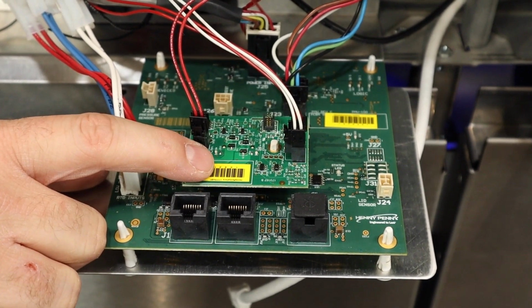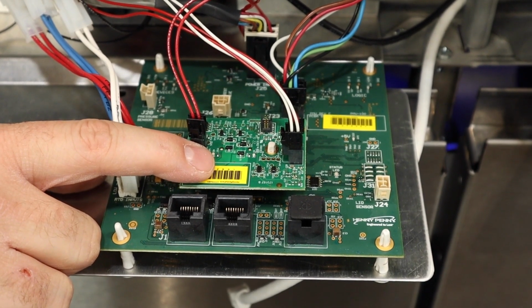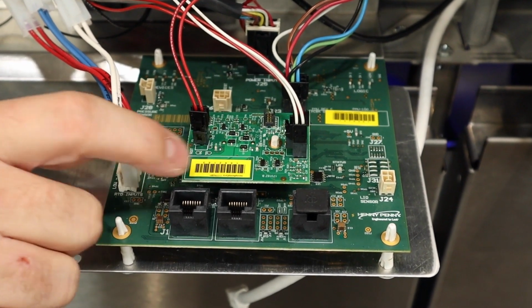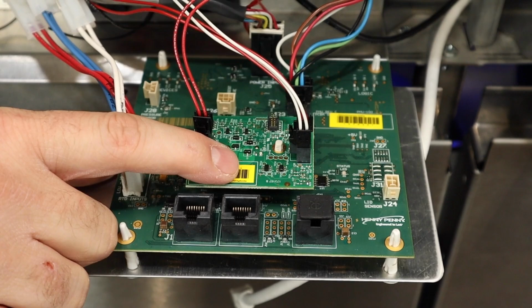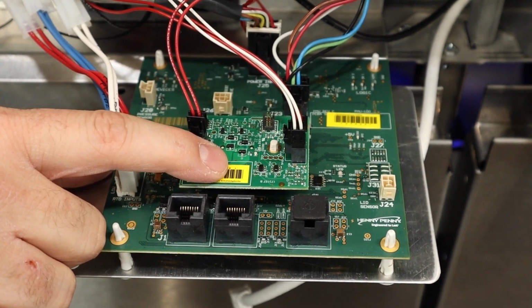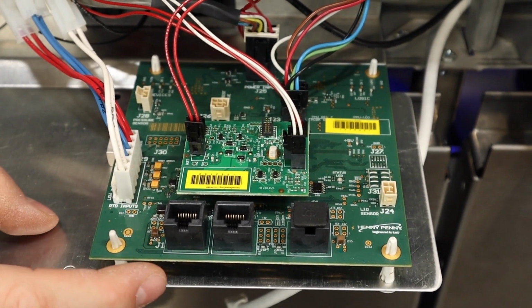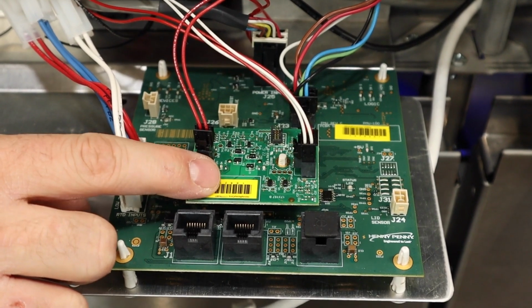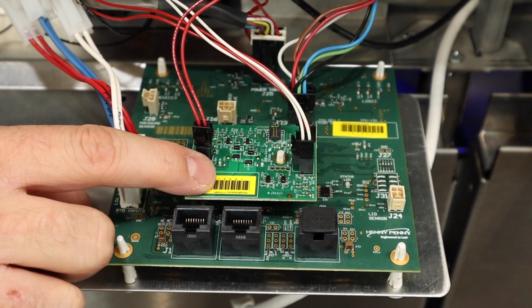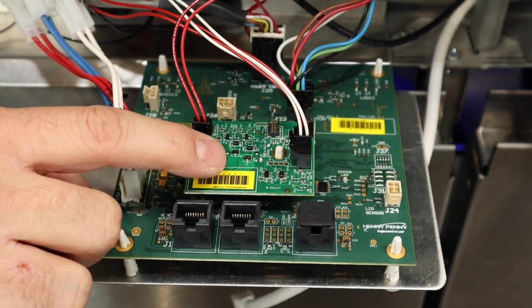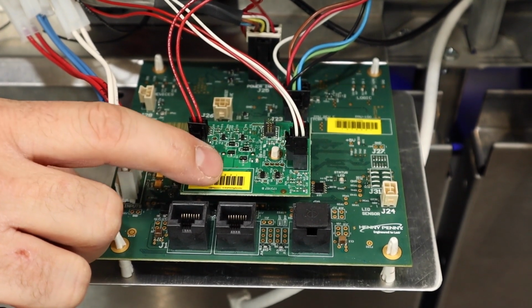Now another error code we could have is an E-10V, as in voltage, and once again that's an internal voltage issue with this high limit PCB, because of course remember our PMU is powering up this PCB with 24 volts DC, and as I mentioned, that's an internal voltage issue with this PCB board.